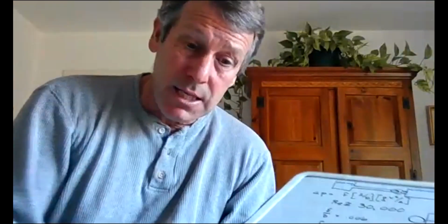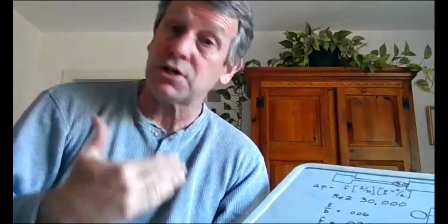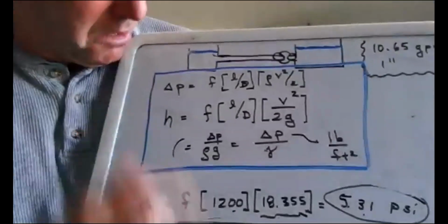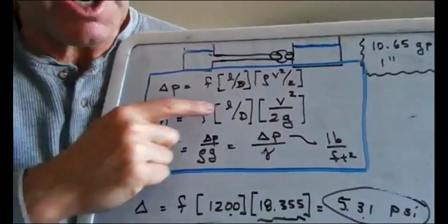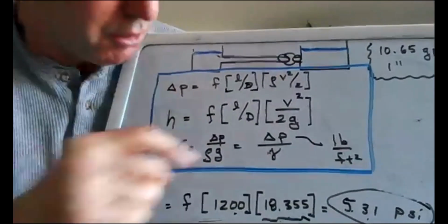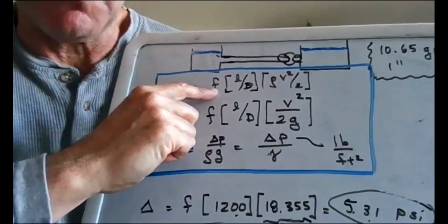But there's one more problem actually, there's several, but the main one is this: the manufacturer likes the pump pressure or the pressure requirement to be specified in that alternative measurement, which is feet. So let's talk about that to finish things off. All right, so quick summary, reminder with one additional detail. If we want to figure out the pressure drop in units of pressure, there's our formula. Just got to be careful with units.